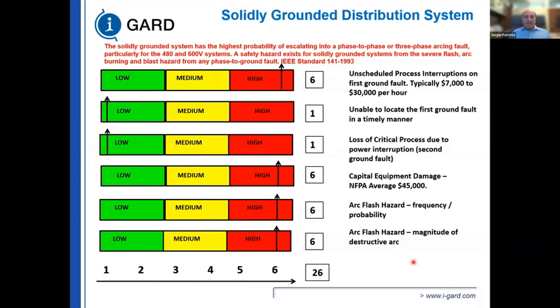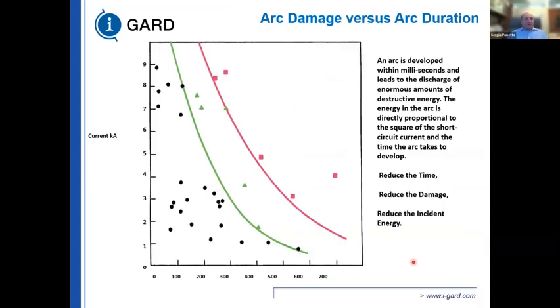This is how it's assessed in this meter. There was a local university that looked at arcing faults. They measured arcing current on this scale in kA and time in milliseconds. For all faults below the green line, of this magnitude and this duration, there was only superficial smoke damage. All faults that occurred between the green line and the red line had minor damage, and all faults above the red line were severe faults and burned through the insulation. So you can see you get as little as 8.5 kA for 300 milliseconds or 3,000 amps for 600 milliseconds. So it doesn't take a lot of arcing damage to cause severe damage to your electrical equipment.